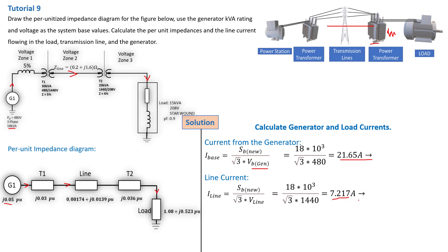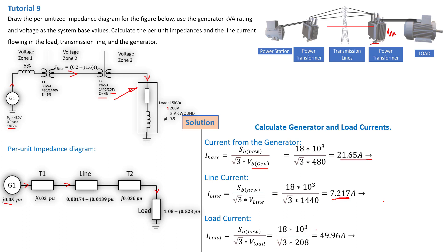The next step is to calculate the current flowing into the load. This current will be different from the transmission line current because we have a step-down transformer — since the voltage is stepped down, the current must shoot up to maintain transformer properties. The load current is I load = S_b(new) divided by (√3 × V load). The motor is at 208 V, so replacing the values: 18×10³ divided by (√3 × 208) gives 49.96 A, basically 50 A.